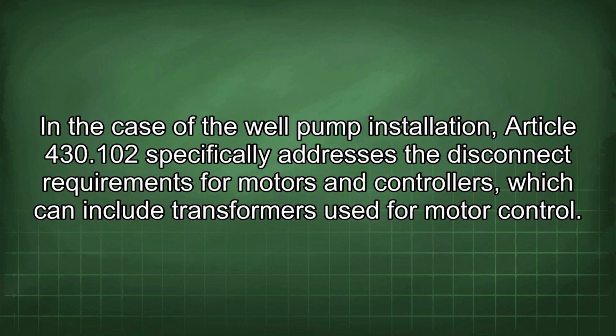In the case of the well pump installation, Article 430.102 specifically addresses the disconnect requirements for motors and controllers, which can include transformers used for motor control.